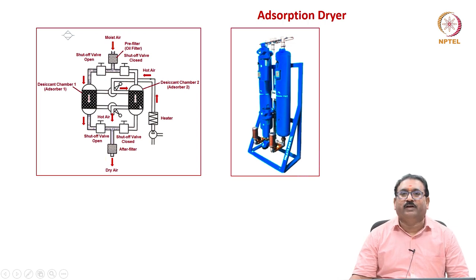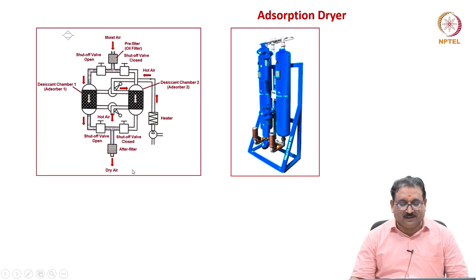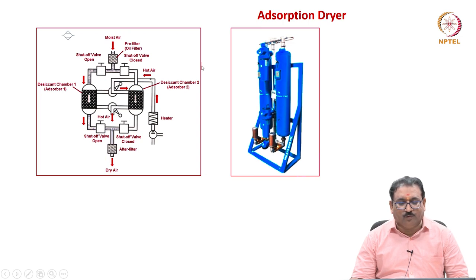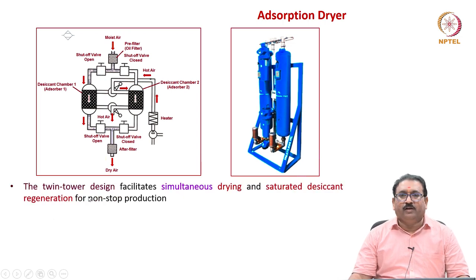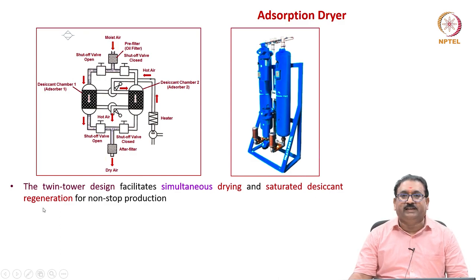One tower is active for drying while the other tower is in regeneration mode. Various filters are there to remove moisture contents. The twin tower design facilitates simultaneous drying and saturated desiccant regeneration for non-stop production. Always either one or the other tower is used for air drying, and the other is used for regeneration.